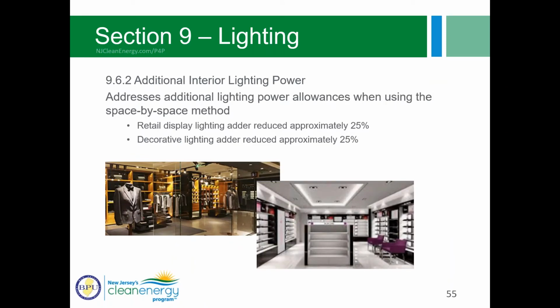Looking through the lighting here, this provision is for additional interior lighting power. We have spaces within retail that have specialty lighting for showcasing different things for sale: furniture, clothing, sporting goods, cars, things like that. There are allowances for additional lighting there, and basically they reduced by about 25%. There's an equation you can use to figure out what type of retail area it is and what that allowance is. So in the 2016 version, it reduces by about 25% for retail and decorative.